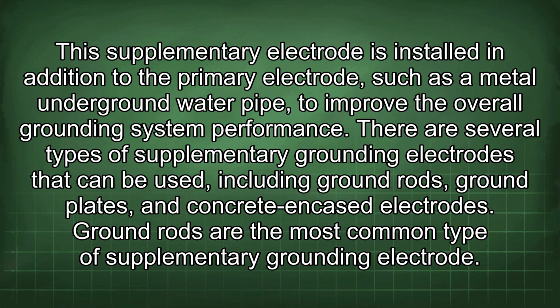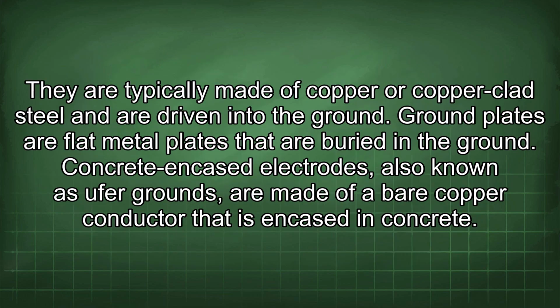There are several types of supplementary grounding electrodes that can be used, including ground rods, ground plates, and concrete encased electrodes. Ground rods are the most common type of supplementary grounding electrode. They are typically made of copper or copper-clad steel and are driven into the ground. Ground plates are flat metal plates that are buried in the ground.